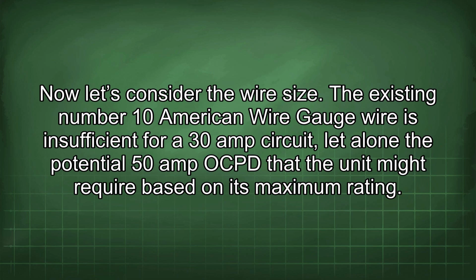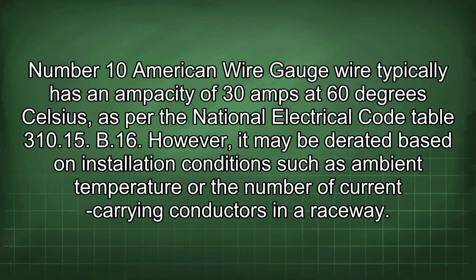Now let's consider the wire size. The existing number 10 American wire gauge wire is insufficient for a 30 amp circuit, let alone the potential 50 amp OCPD that the unit might require based on its maximum rating. Number 10 American wire gauge wire typically has an ampacity of 30 amps at 60 degrees Celsius, as per the National Electrical Code Table 310.15(B)(16). However, it may be derated based on installation conditions such as ambient temperature or the number of current carrying conductors in a raceway.